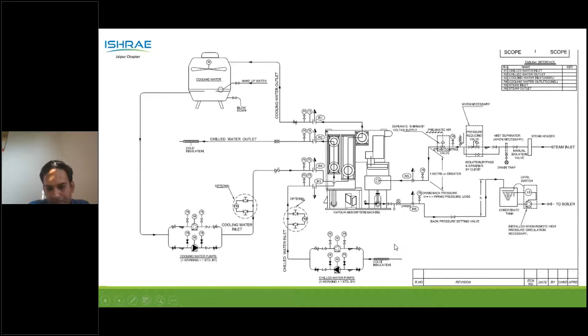There is a steam control valve which is a part of the vapor absorption machine, which helps the VAM to unload from 100% to 10%; the unloading is through a steam control valve. The steam is going inside the vapor absorption machine, you can see, and what comes out is 80 to 90 degrees Celsius condensate, which is pure water, which can go into a condensate tank, and then it can be pumped to the boiler or internally to your process.